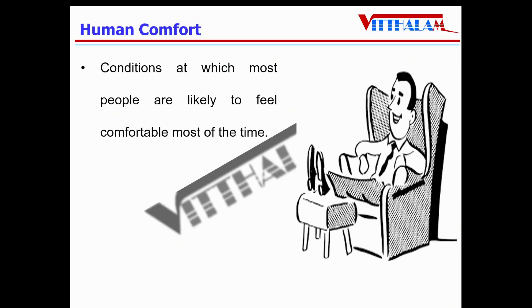Then human comfort. It is the condition at which most people are likely to feel comfortable most of the time. Also known as thermal comfort. The range as far as dry bulb temperature is concerned, it is 22 to 27 degrees Celsius, and the RH will be 40% to 60%.